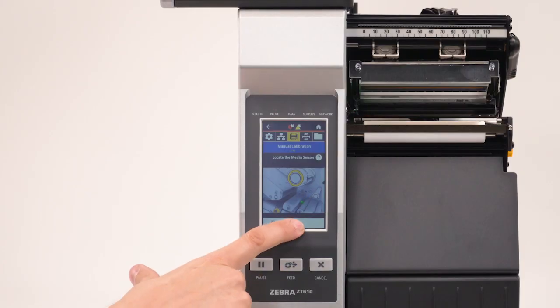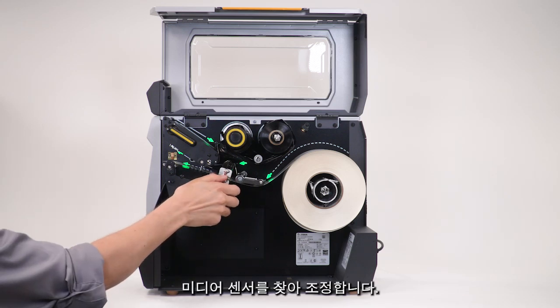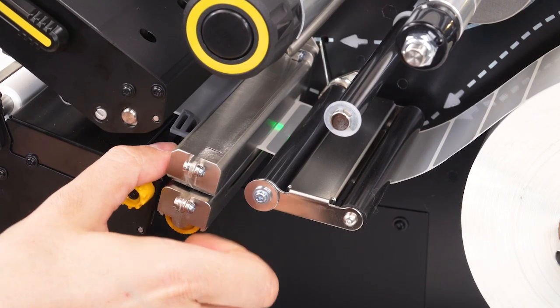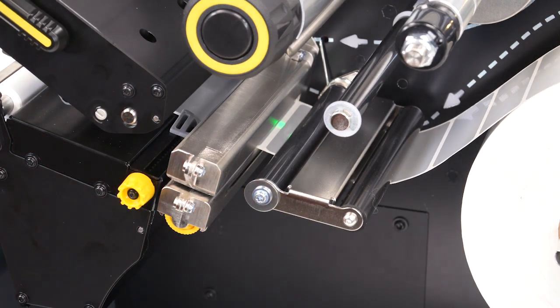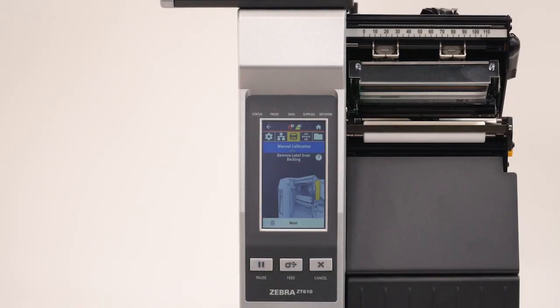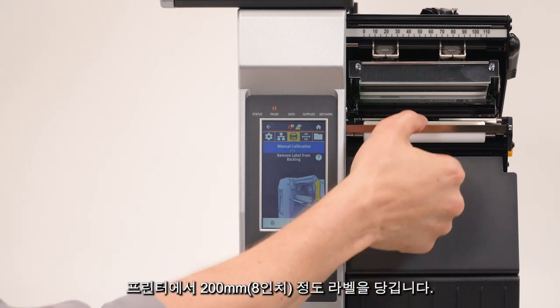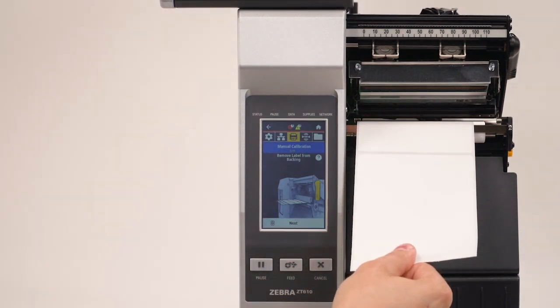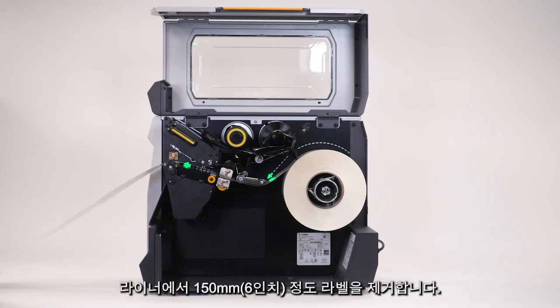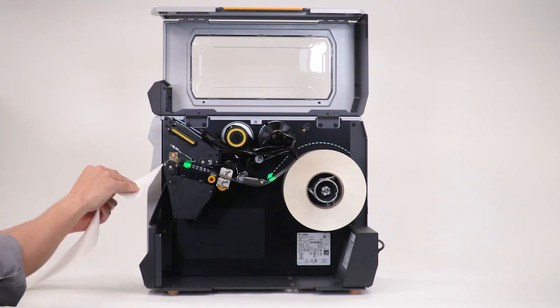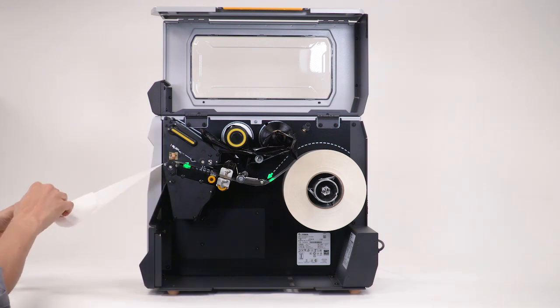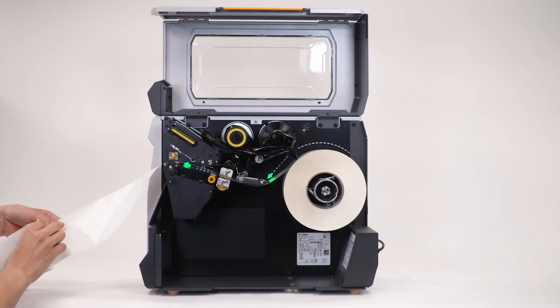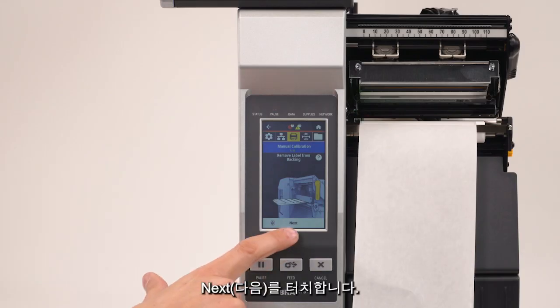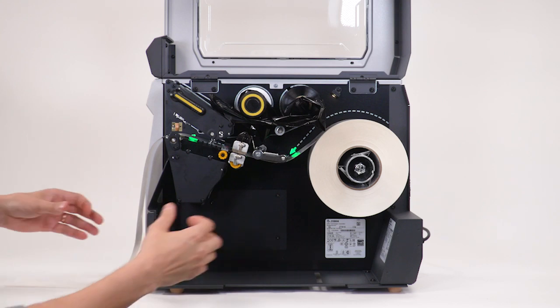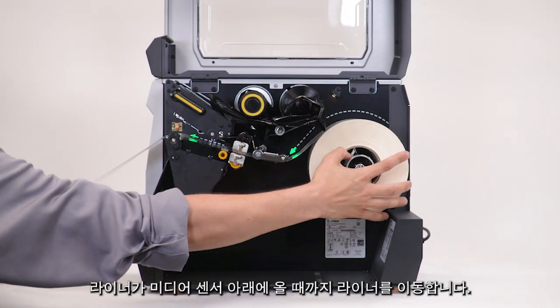Touch Next. Locate and adjust the media sensor. Touch Next. Pull about 8 inches or 200 millimeters of labels from the printer. Remove about 6 inches or 150 millimeters of labels from the liner. Touch Next. Move the liner until it is under the media sensor.